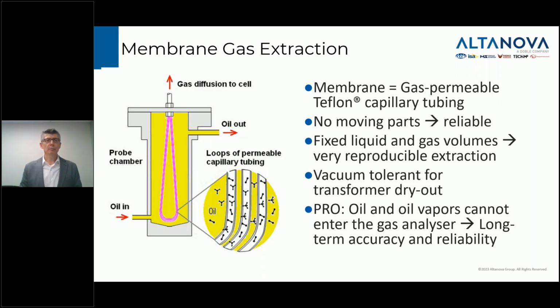Nice thing about membrane gas extraction, there's no moving parts, so they're very reliable. The volume ratios are fixed, so you get very reproducible extraction over time. They're tough. They can withstand vacuum. If you're doing a vacuum dry-out on a transformer and you forget to valve off the monitor, it's not a problem. It won't cause any damage to the extraction system. It won't move oil from one place to another either.